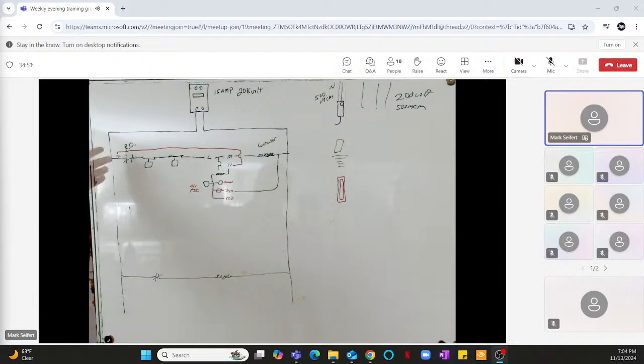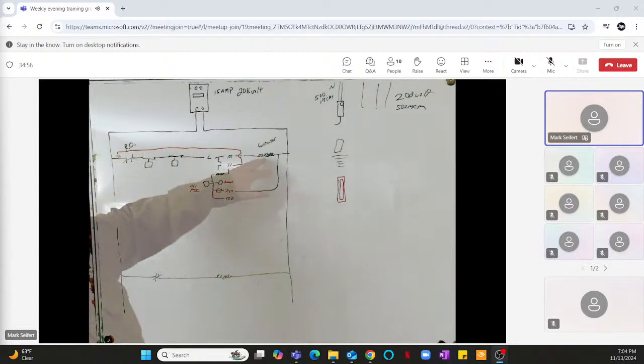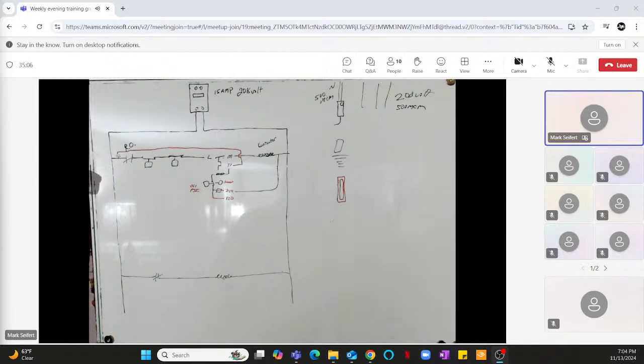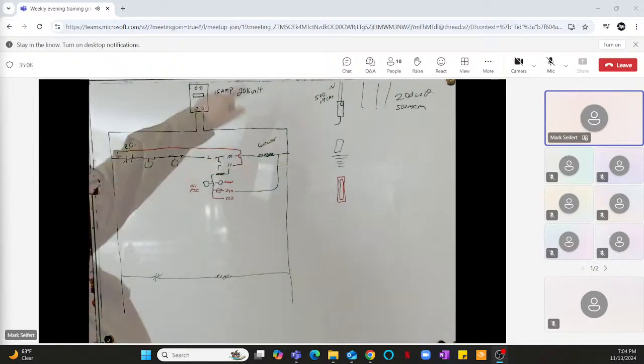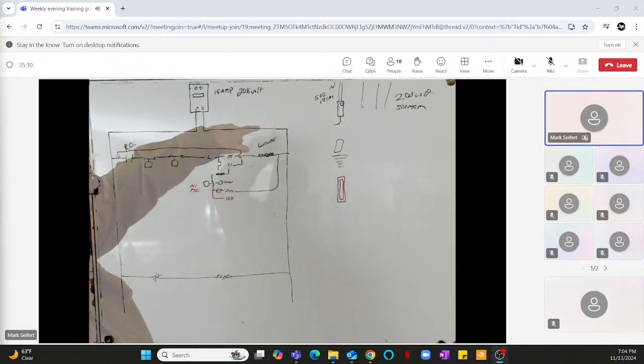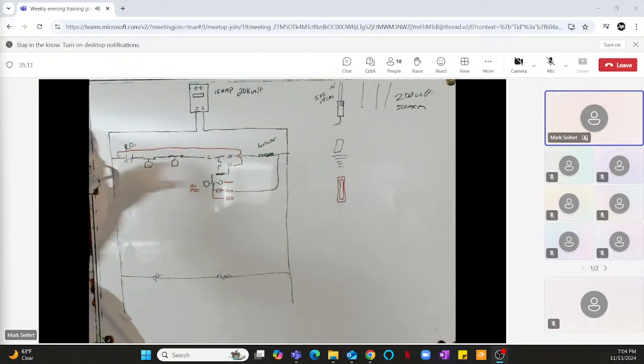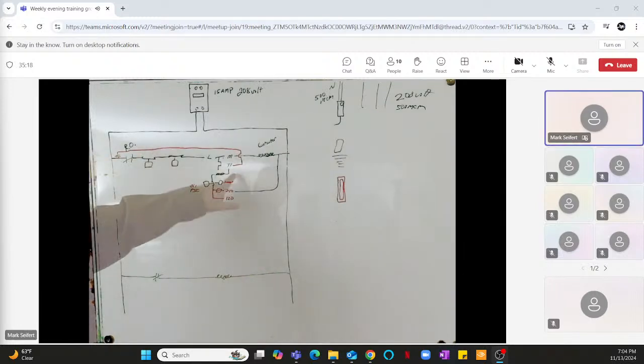The good thing about that is it will not ever trip if the compressor is not running. So it does away with a lot of oil fail nuisance calls. Let's say the compressor breaker is tripped and the compressor's not running, even though the contactor's pulled in, it's never going to give the power over here to run the heater to trip it on oil fail. So keep that in mind when you're troubleshooting these things.